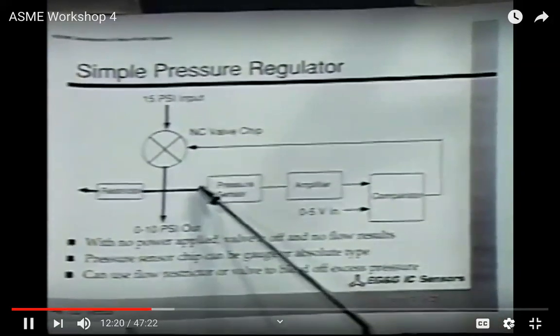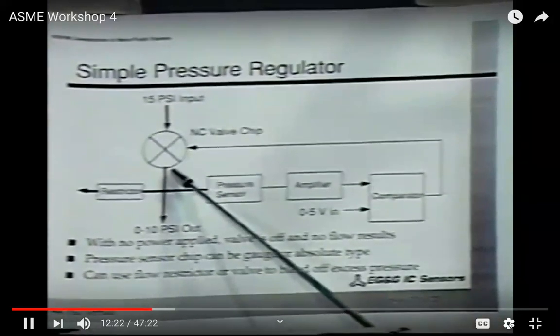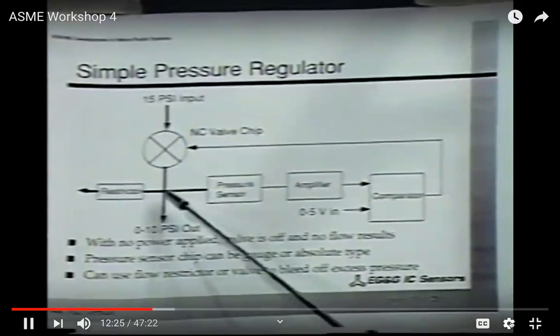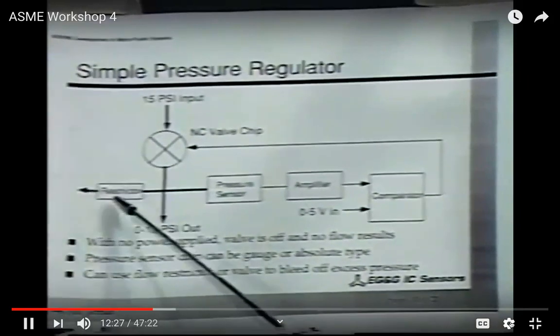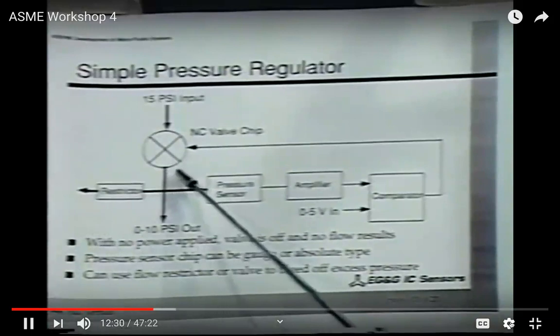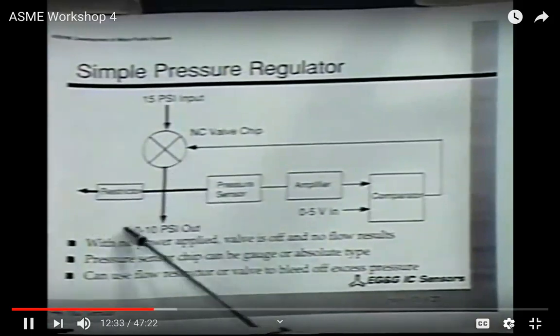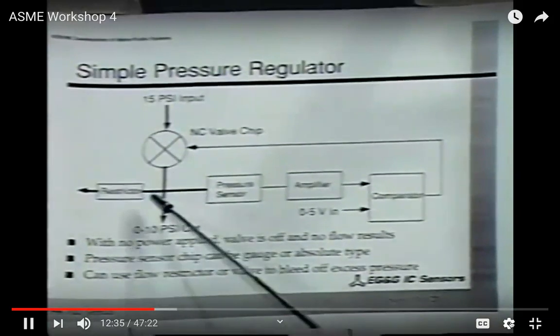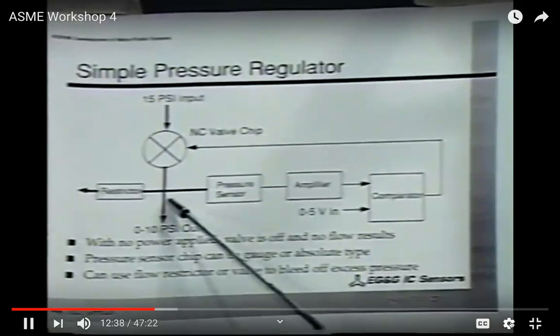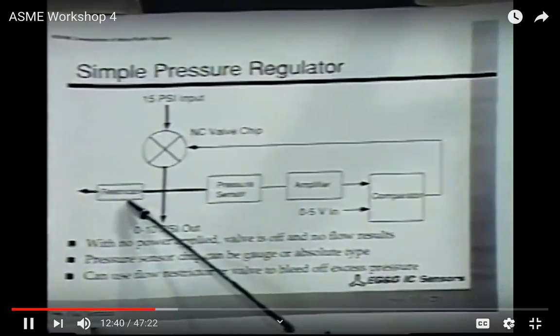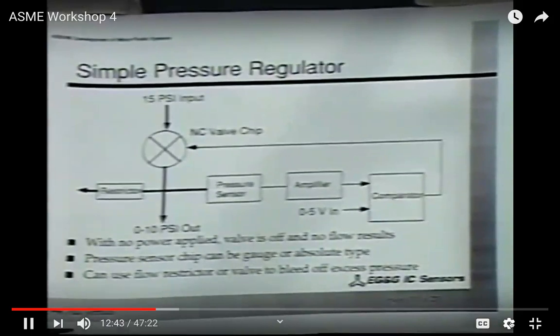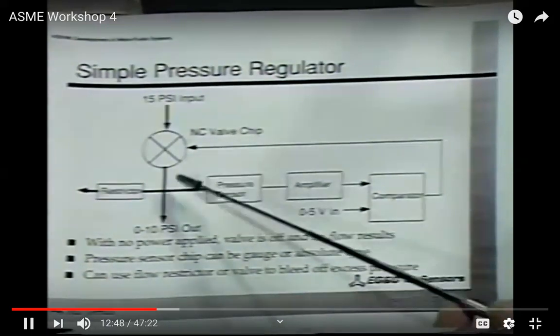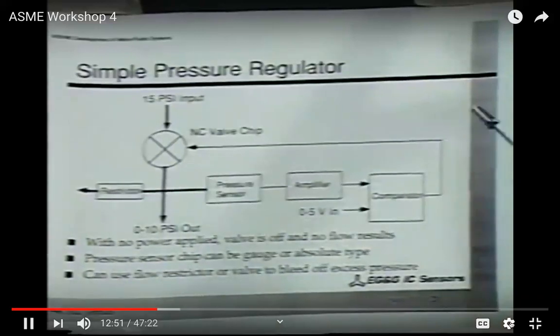If the pressure is lower than desired, the valve opens, increasing the pressure. We also include a silicon restrictor chip, since if you want to decrease the pressure, whether or not there's flow going out to the system, you need to vent a small amount of gas to reduce the pressure. We use a silicon flow restrictor for that purpose. With no power applied to the system, there's no output flow due to the normally closed valve.